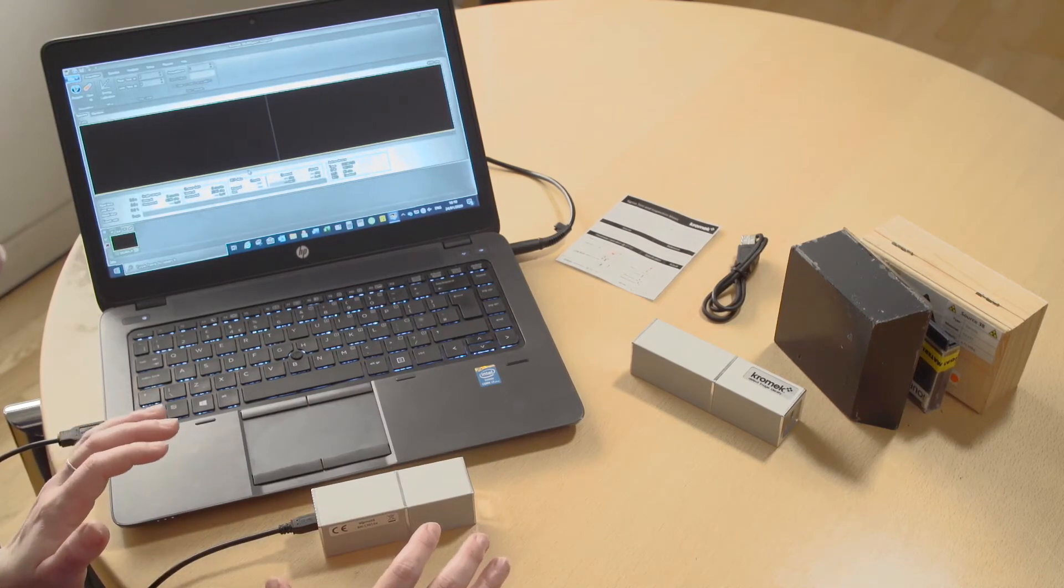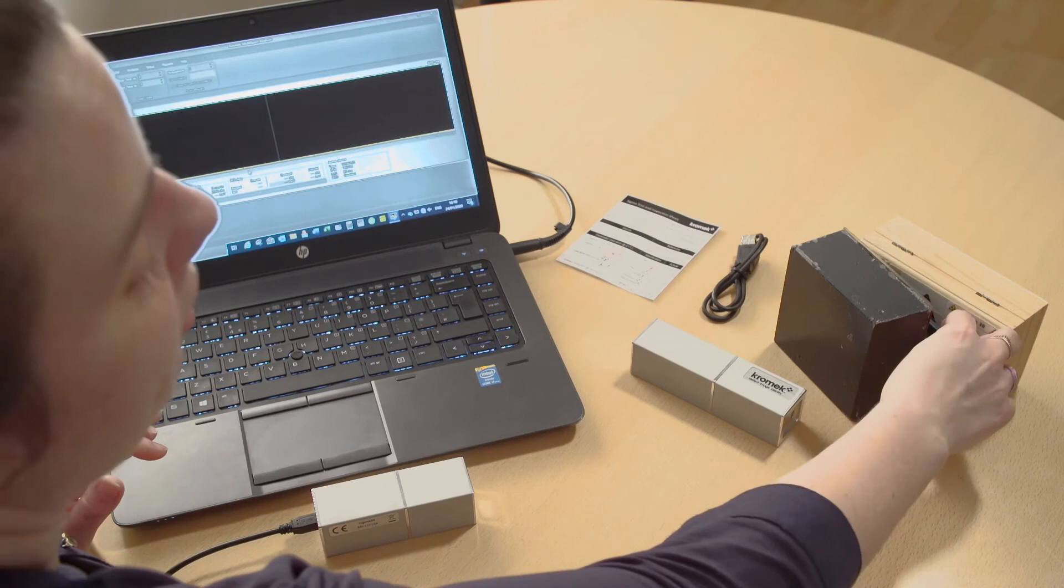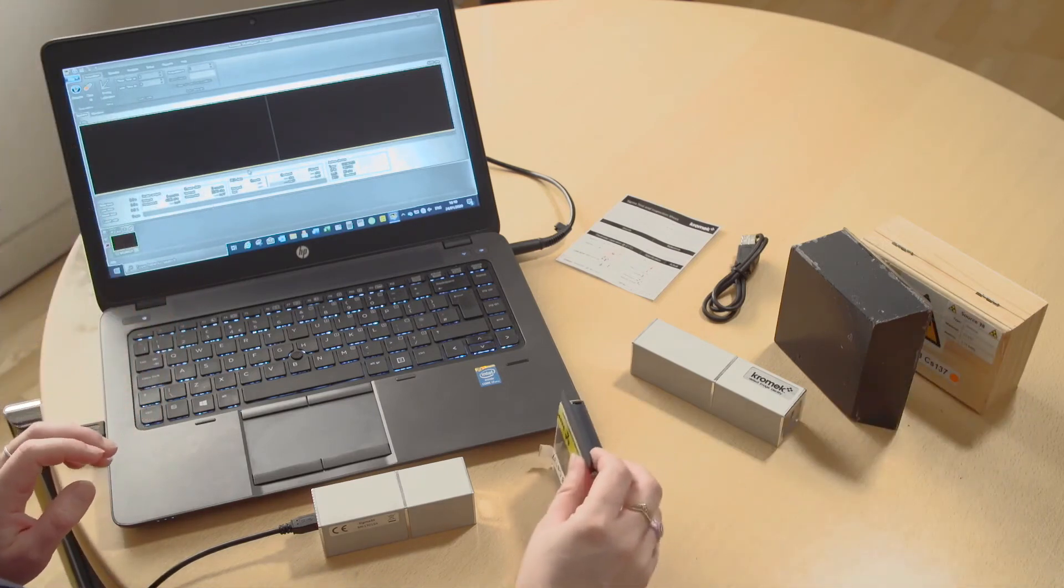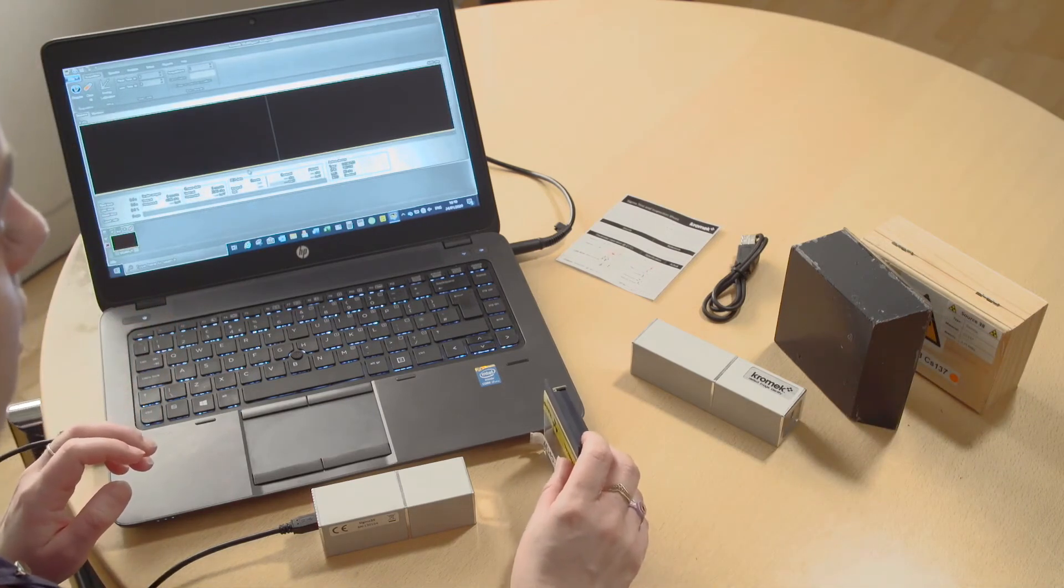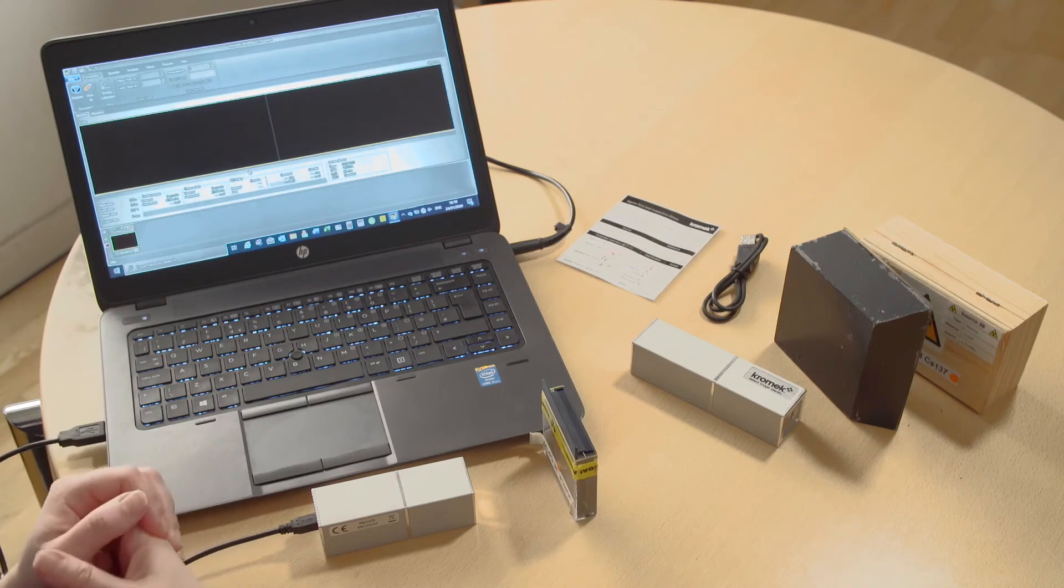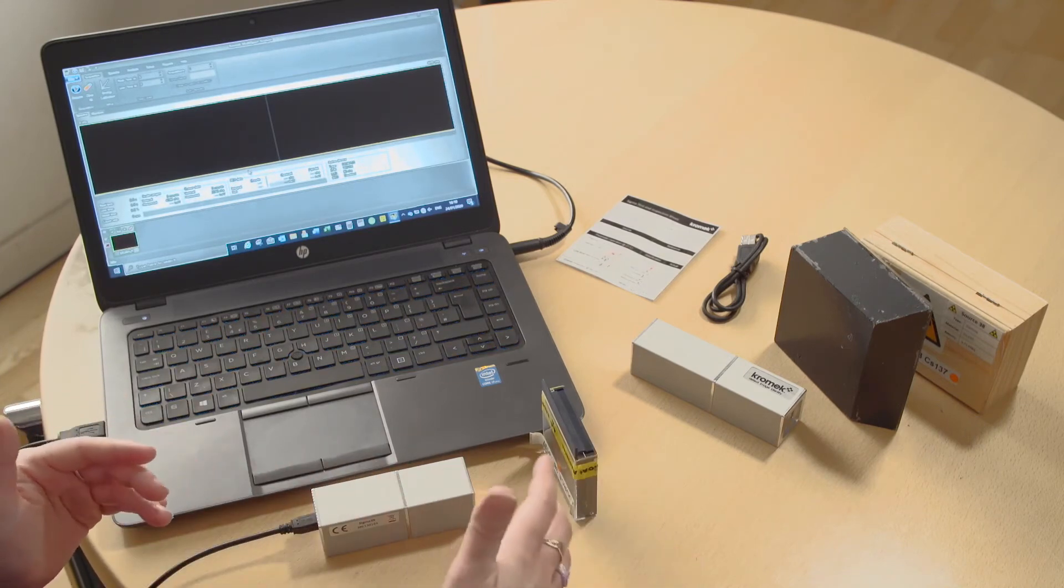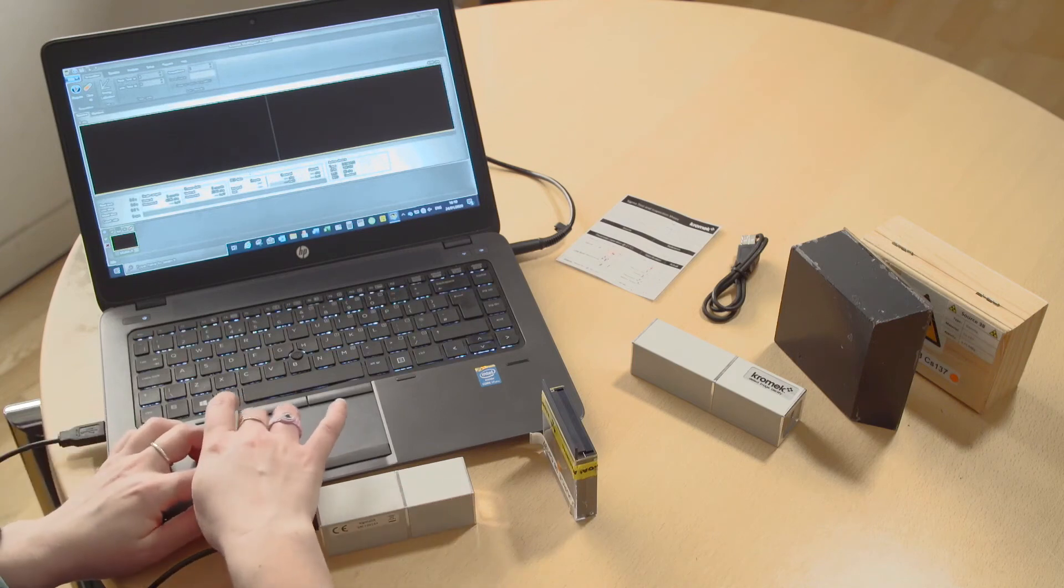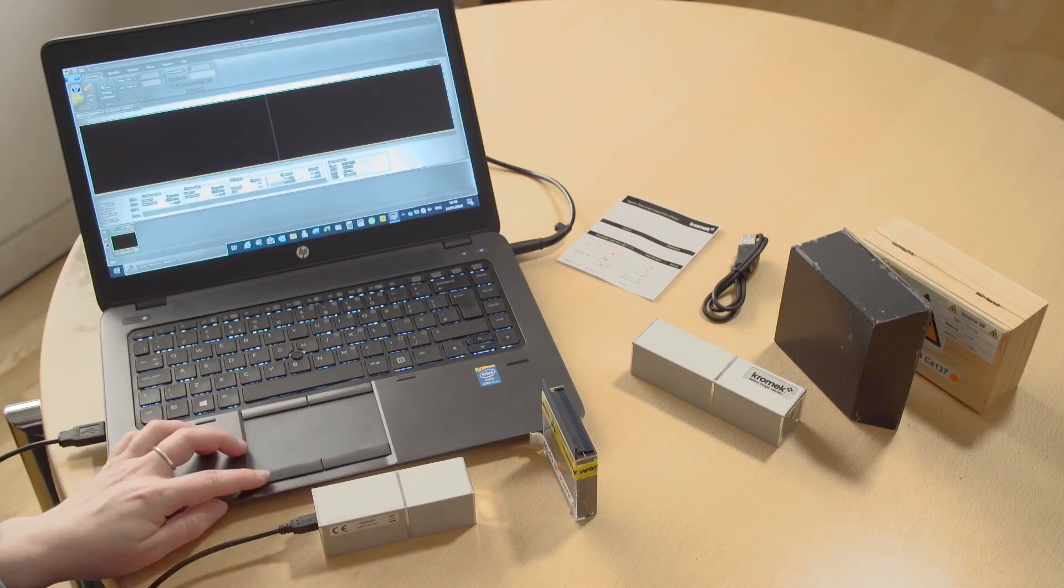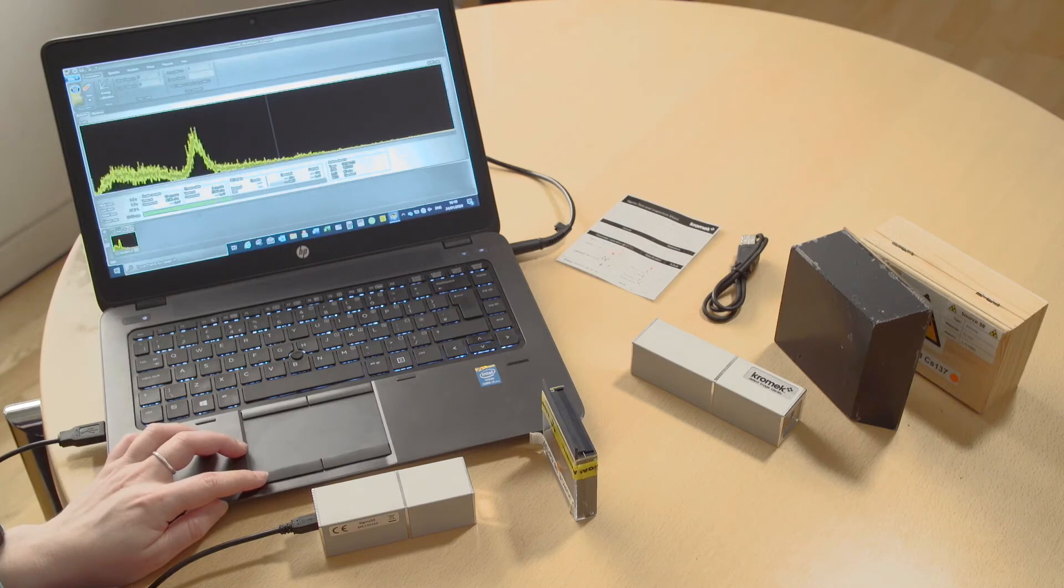Give it a little while to settle, a minute or two will be fine once you have plugged it in. Then if you want to test a sample or use a source with it, simply put the sample or the source in front of it, press acquire on the software and then you will get a spectrum.